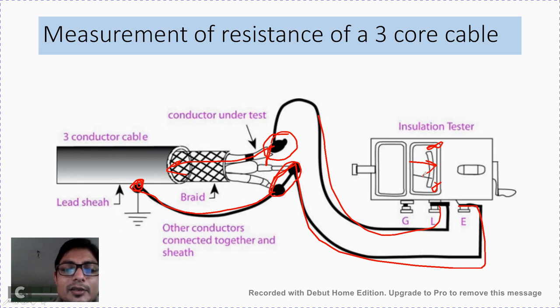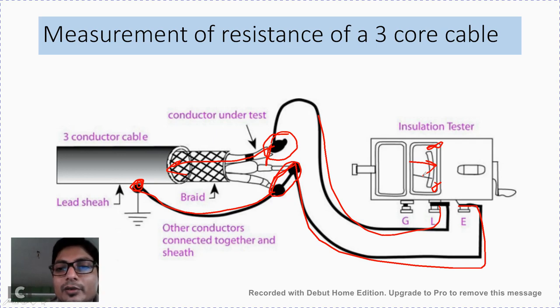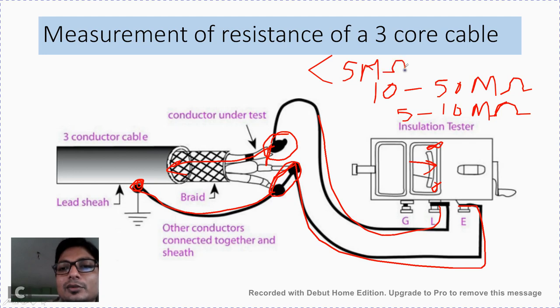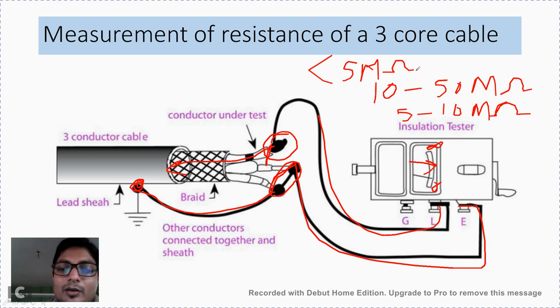Once we confirm the insulation resistance meets the required values, the cable can continue in operation. Good insulation resistance is between 10 to 50 mega ohms. A value between 5 to 10 mega ohms is considered abnormal. Once it falls below 5 mega ohms, the insulation is in a critical condition and the cable must be replaced completely to ensure safe and proper operation.